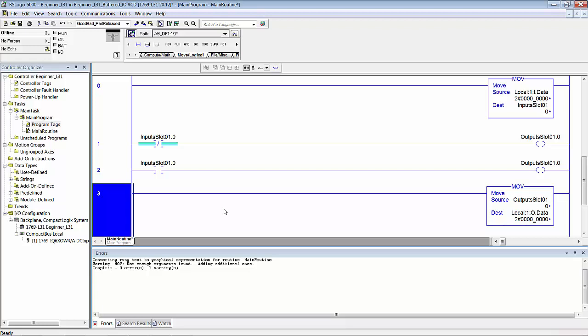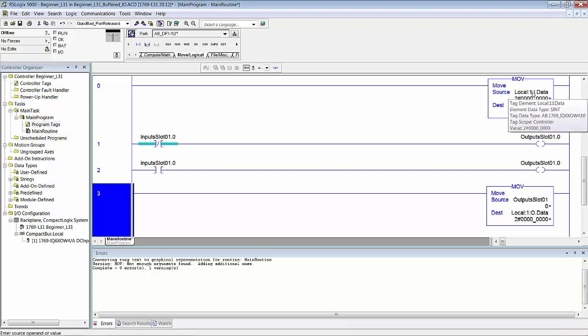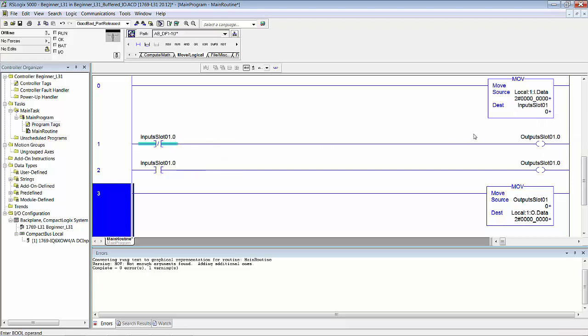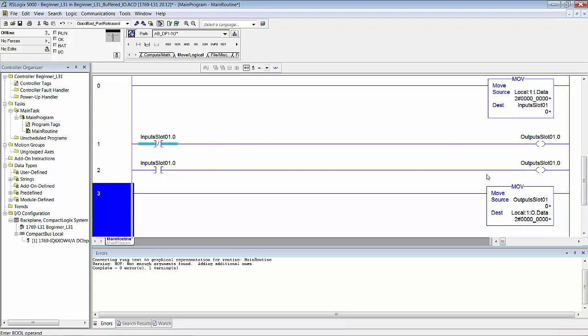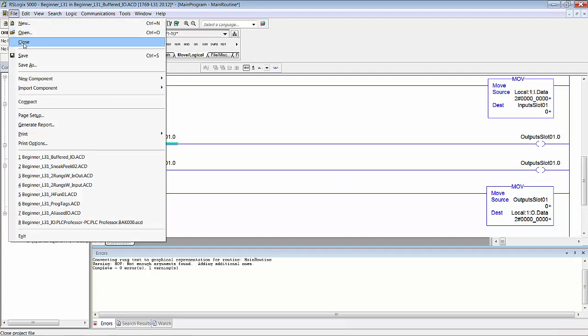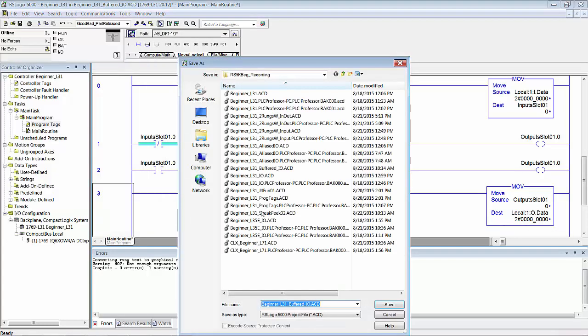If you read down through those rungs, you could say that at the beginning of the program scan in rung zero, the inputs are refreshed—or rather this tag, its bits are refreshed by that instantaneous state of that word. Then using that refreshed internal tag we run our logic, and then once we're done with the logic we take the results of the logic, we move it into an actual module-defined tag, and out it goes to the output cards. I just saved this program as InOutBuffered.